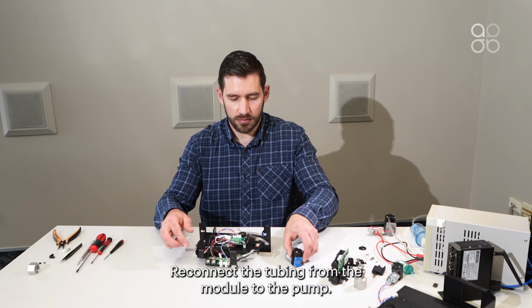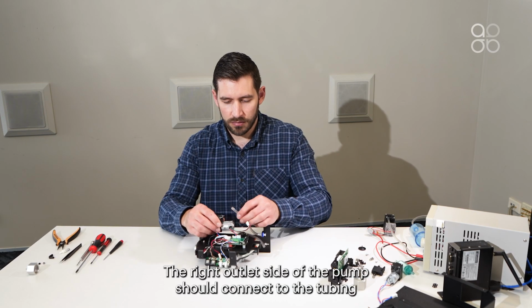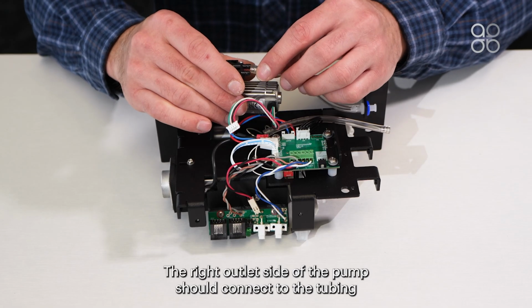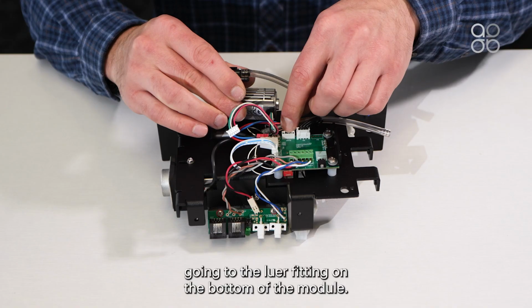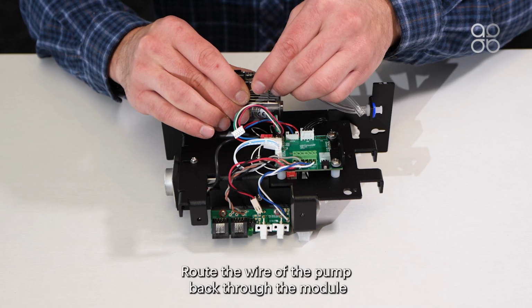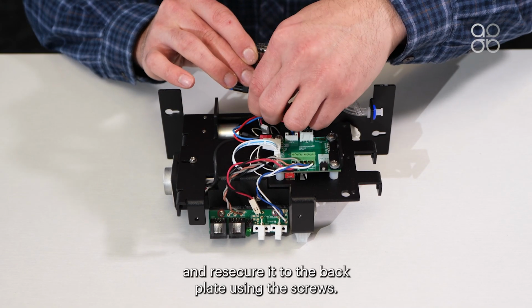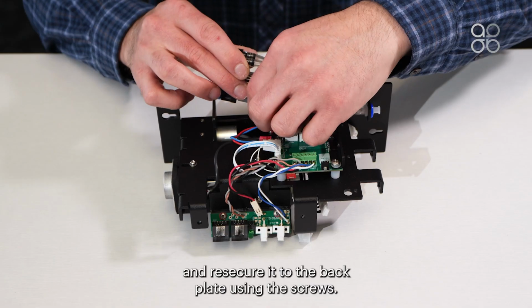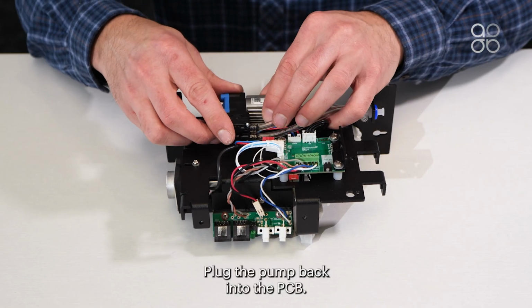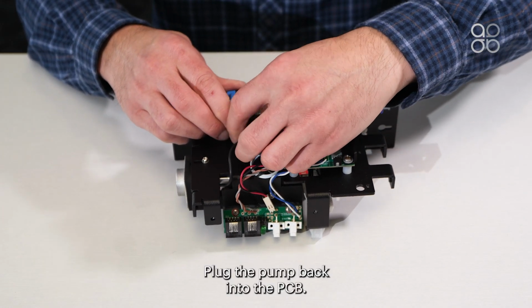Reconnect the tubing from the module to the pump. The right outlet side of the pump should connect to the tubing going to the luer fitting on the bottom of the module. Route the wire of the pump back through the module and resecure it to the backplate using the screws. Plug the pump back into the PCB.